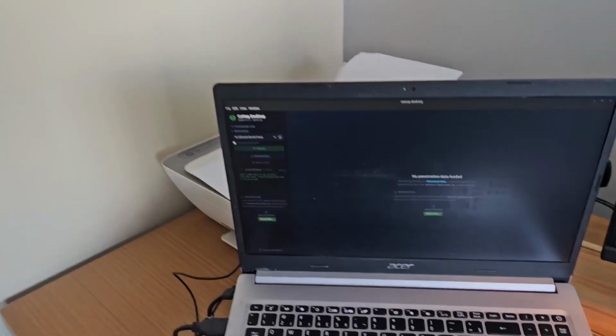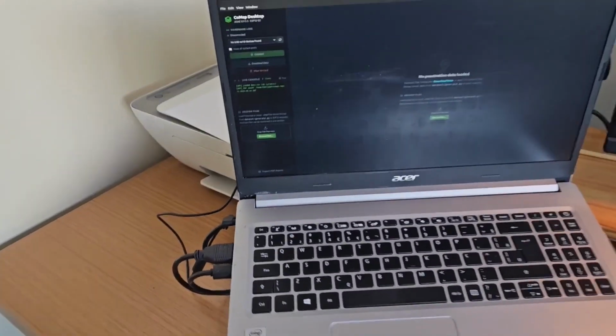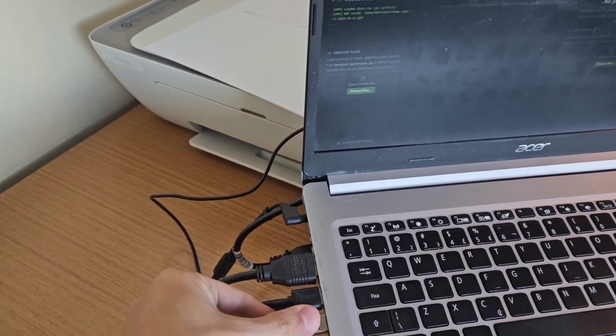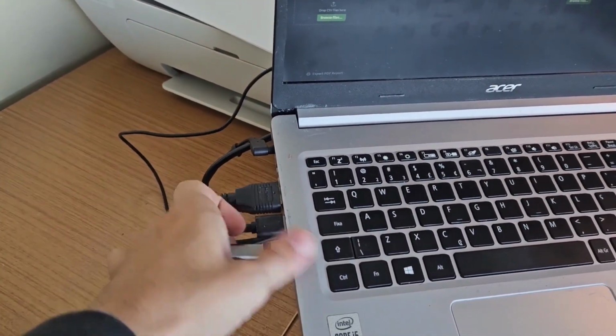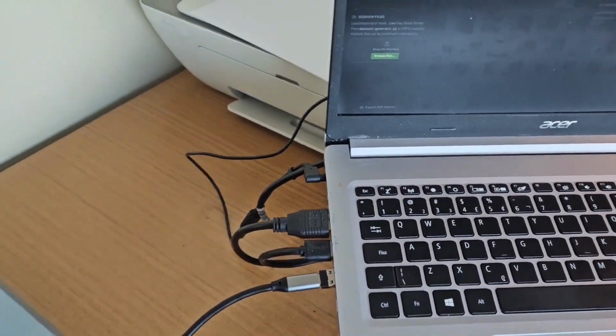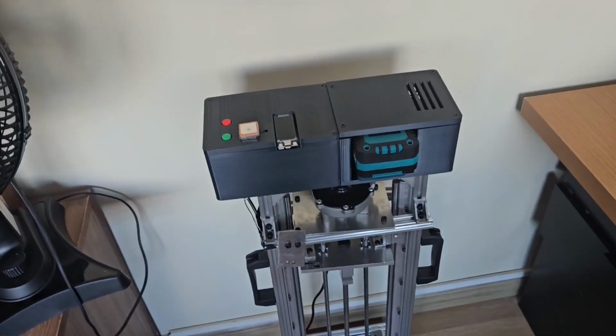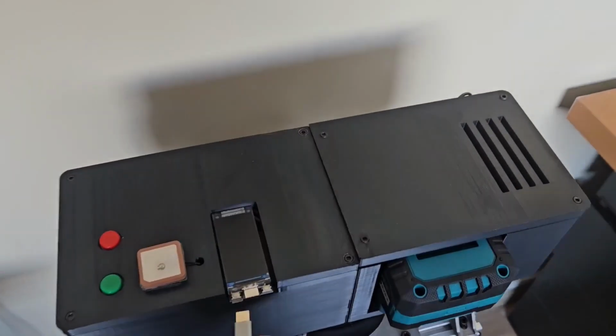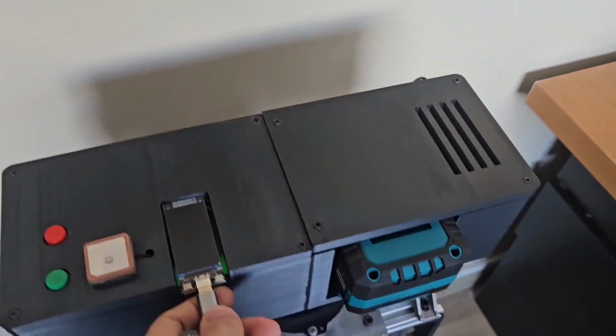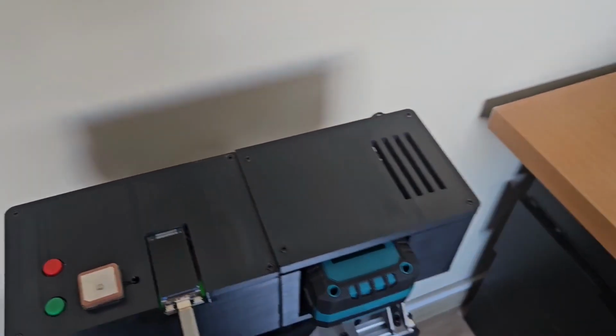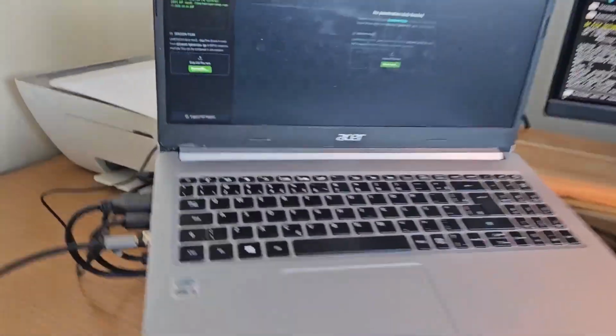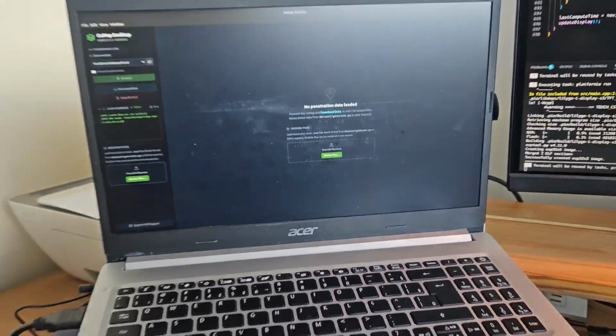Once you have finished taking your measurements, get your physical penetrometer next to a computer and connect to it using a USB Type-C cable, connecting one end to the computer and the other end to the controller board, the ESP32. Now it's time to use the CoMap desktop application for the data analysis.